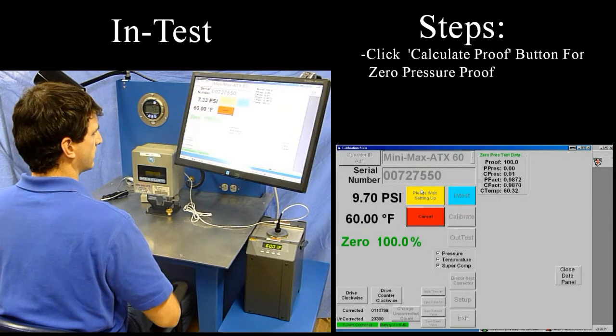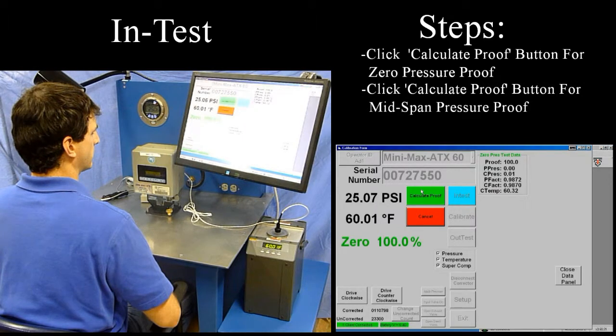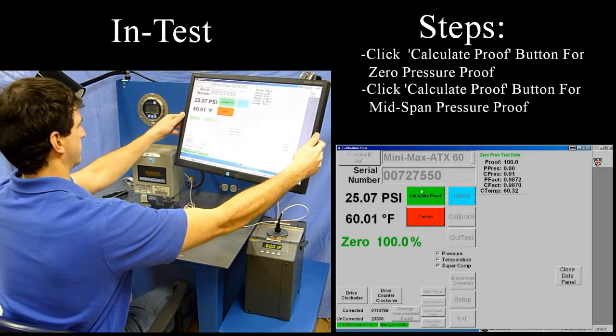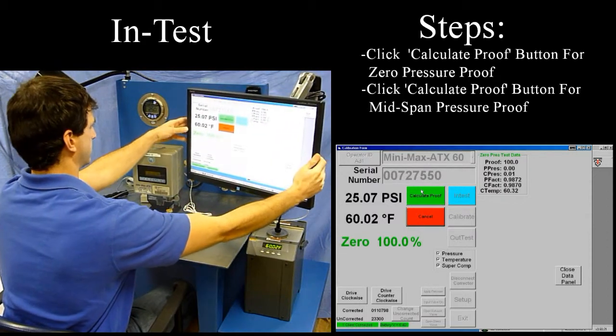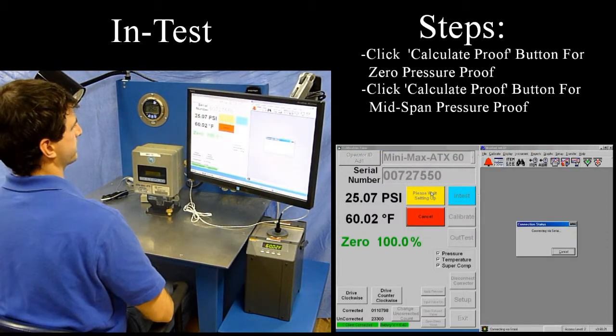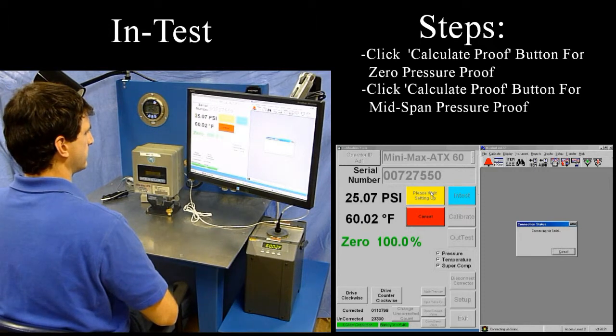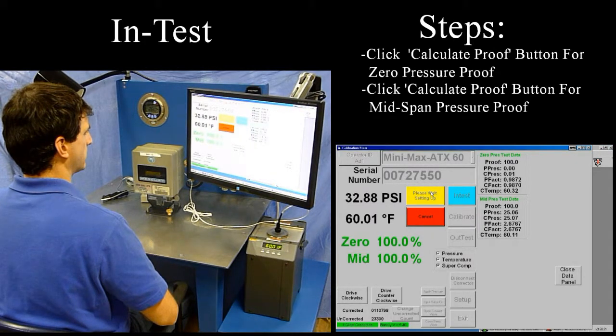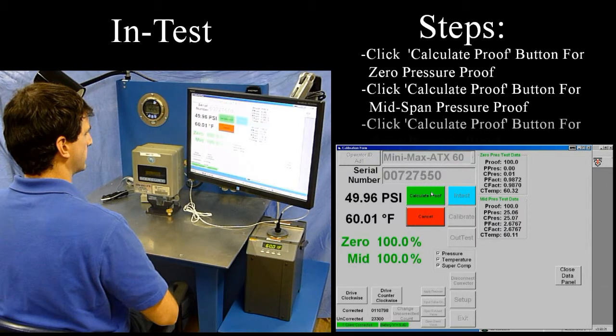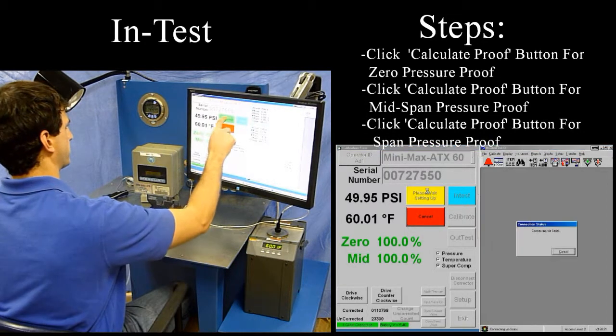The zero pressure proof is displayed on screen with a detailed list of readings from both the on-stand sensors and the corrector sensors. The proof will appear in green if it is within the limits set by the operator in the setup menu. The test continues to the mid-span and full-span pressure tests, each time displaying the data neatly in the data panel. The test can be aborted at any time by pressing the cancel button.